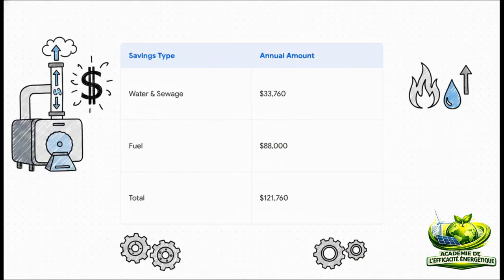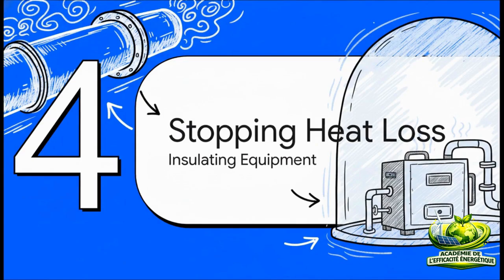And man, these savings pile up fast. Let's say you manage to return just an additional 10,000 pounds per hour of hot condensate back to your boiler. You're looking at saving roughly $34,000 in water and sewage costs alone, plus another $88,000 in fuel energy. That is over $120,000 back in your pocket every single year. It just goes to show how optimizing your water recovery is absolutely tied to your overall fuel efficiency. All right, let's talk about our fourth zone, stopping distribution heat loss.